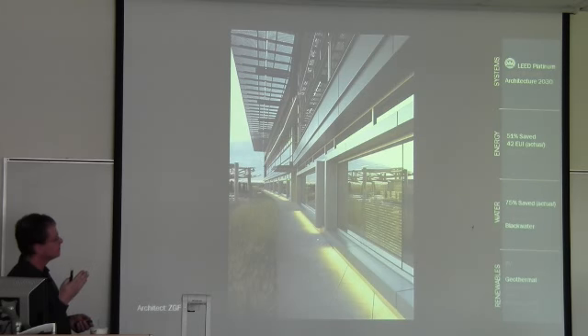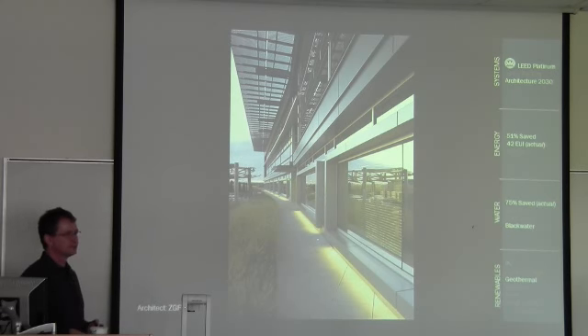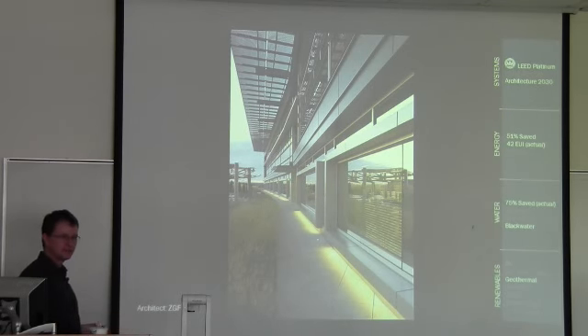automated solar sensing device on the roof that knows the time of day, knows the azimuth of the sun, and takes in the intensity of the sun, and then automatically pitches these blinds to provide the right amount of shading and the ability to bounce the light up for intrusion of daylighting. So lots of systems went into the building, but again, like the north side, on this south side we made all these changes, and what we got rid of was supplemental cooling zones on the south, because we made enough change that we could look at the interior environments and justify that we didn't need those exterior zones. So that simplified the mechanical system, but it takes a lot of work, working with the engineer and the architect, to bring that into effect.